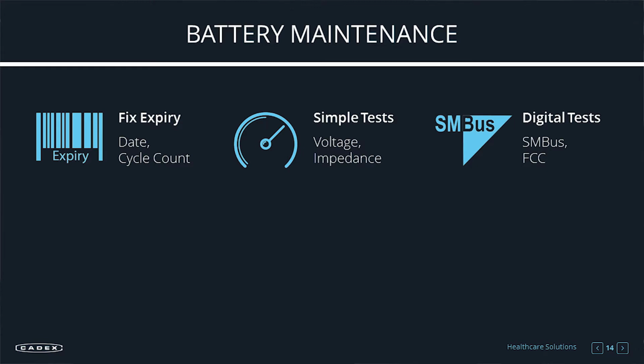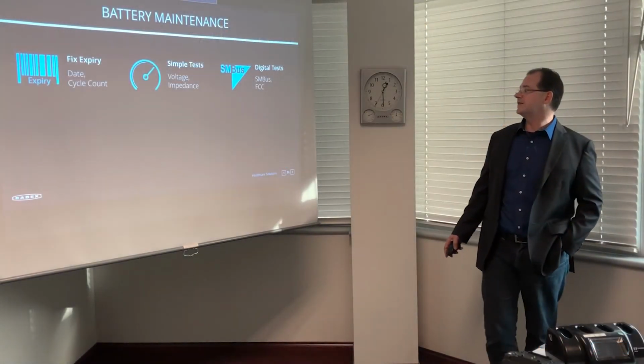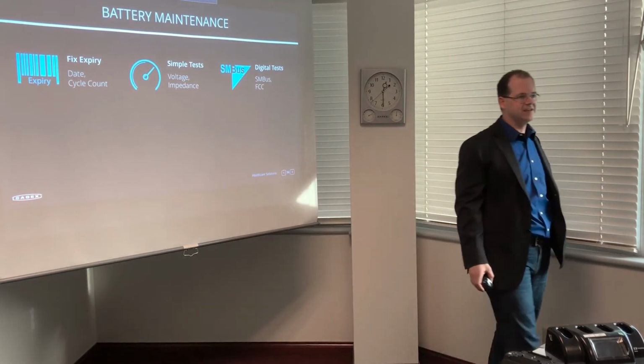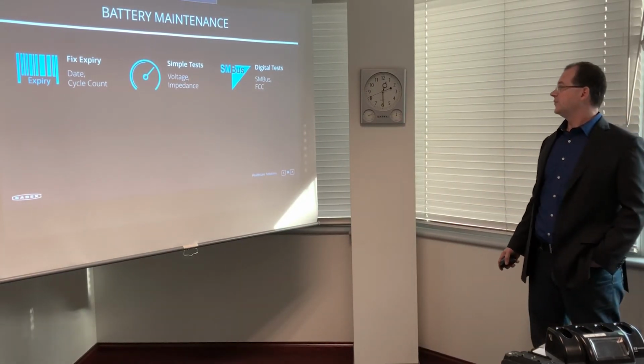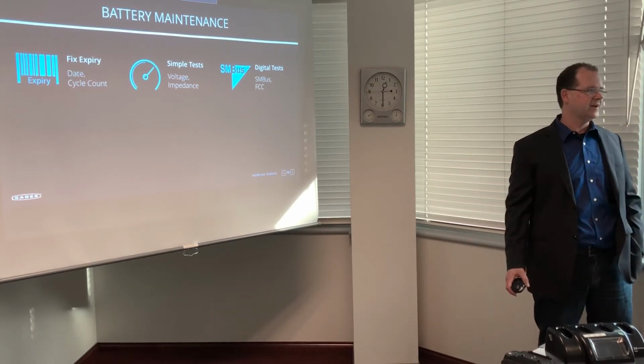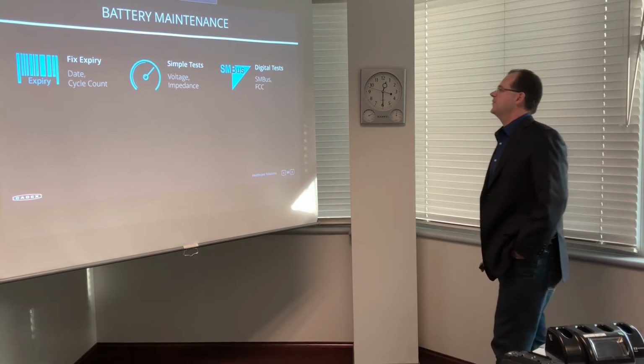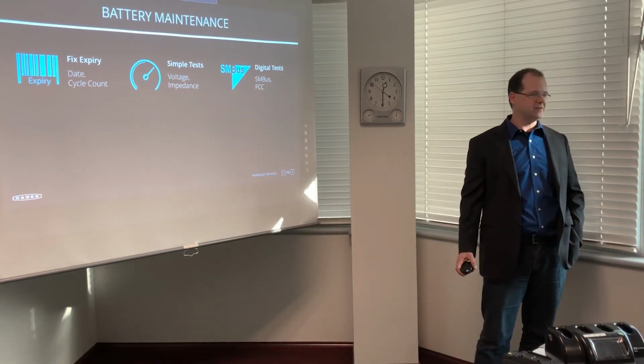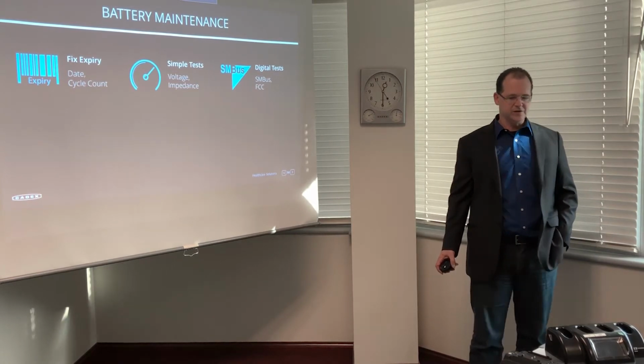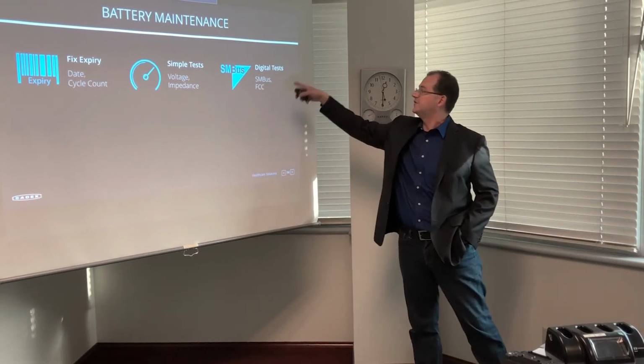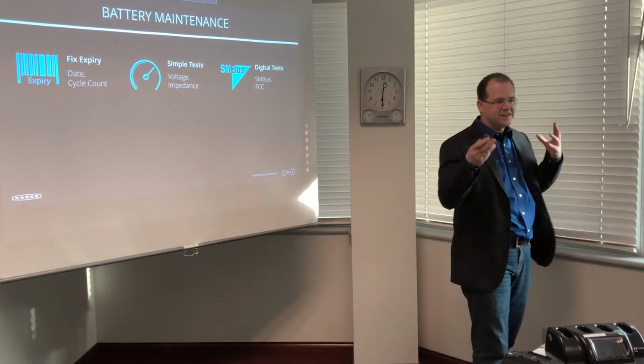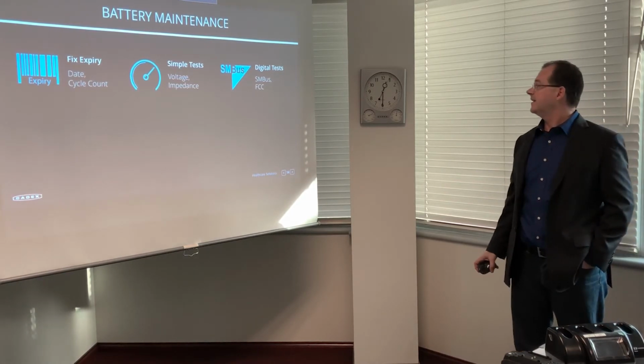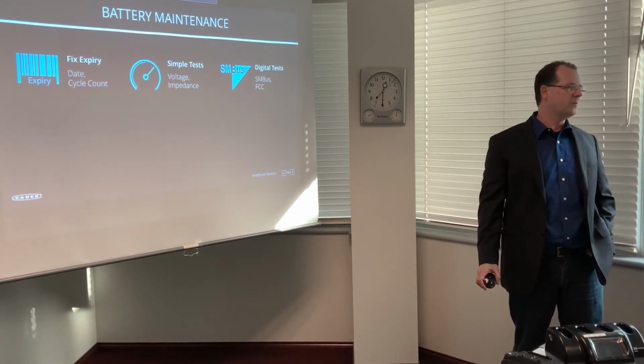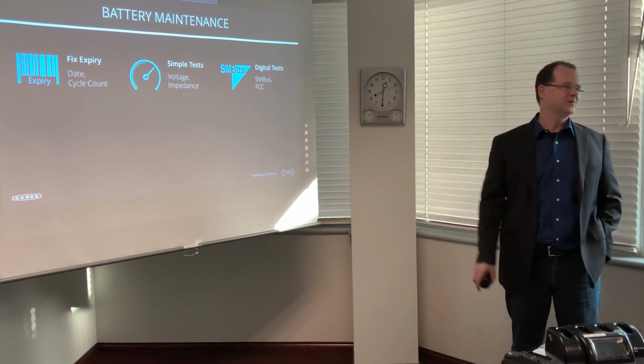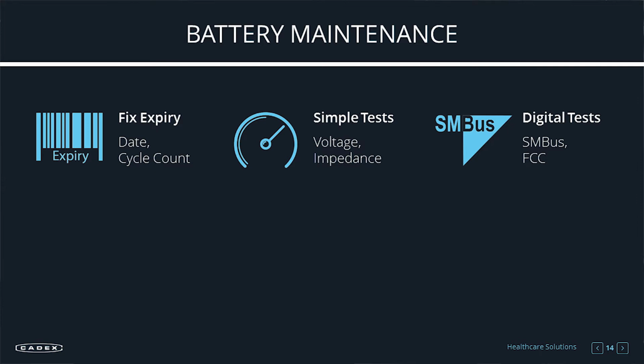And then the third one, which is emerging, is the whole SM bus, using the digital models built into the gas gauge of the battery. Those are coming more and more, but they're still quite unreliable, and they don't necessarily meet the verification and validation requirements of the FDA. So we've seen some of our customers actually want to drive these decisions through the full charge capacity, which is essentially something like state of health in the SM bus, but then ultimately pull back and go back to voltage-based solutions or fixed expiry solutions, because they say we just don't understand all possible use scenarios of this battery.